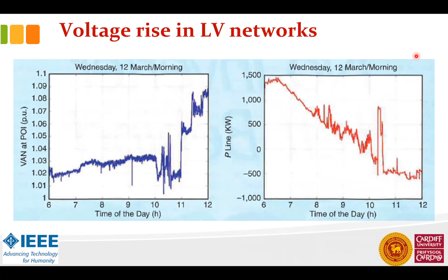Other local networks are having real issues with voltage rise. What I'm showing you is a feeder in Australia. Sorry, a feeder in Germany. Early in the morning, the voltage at the beginning of the feeder is 1.02, and the consumers are absorbing electric power of around 1,500 kilowatts.